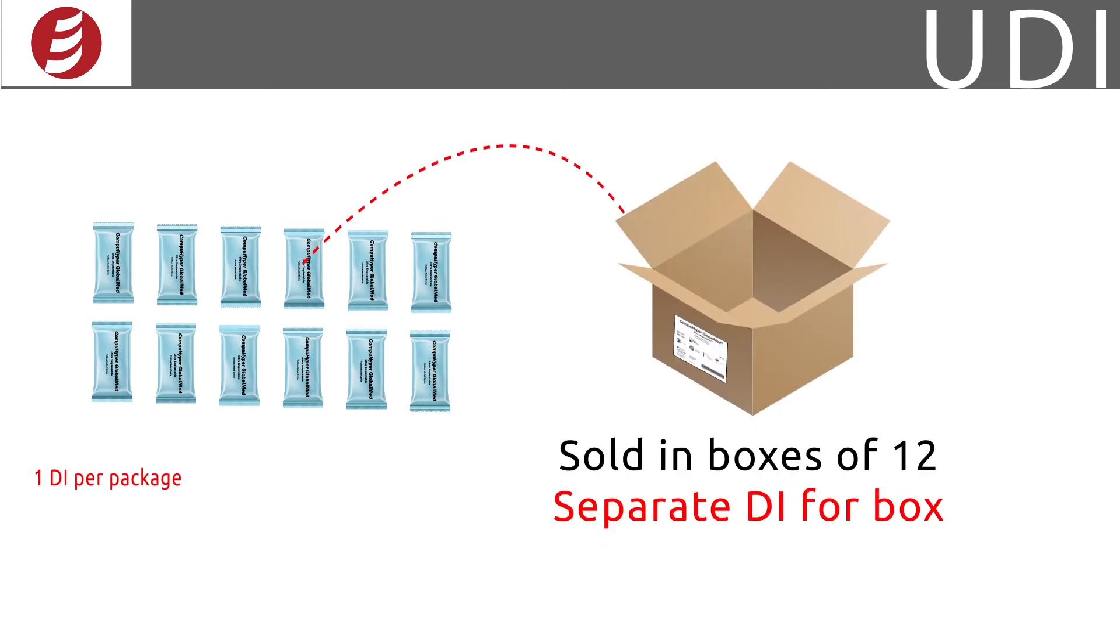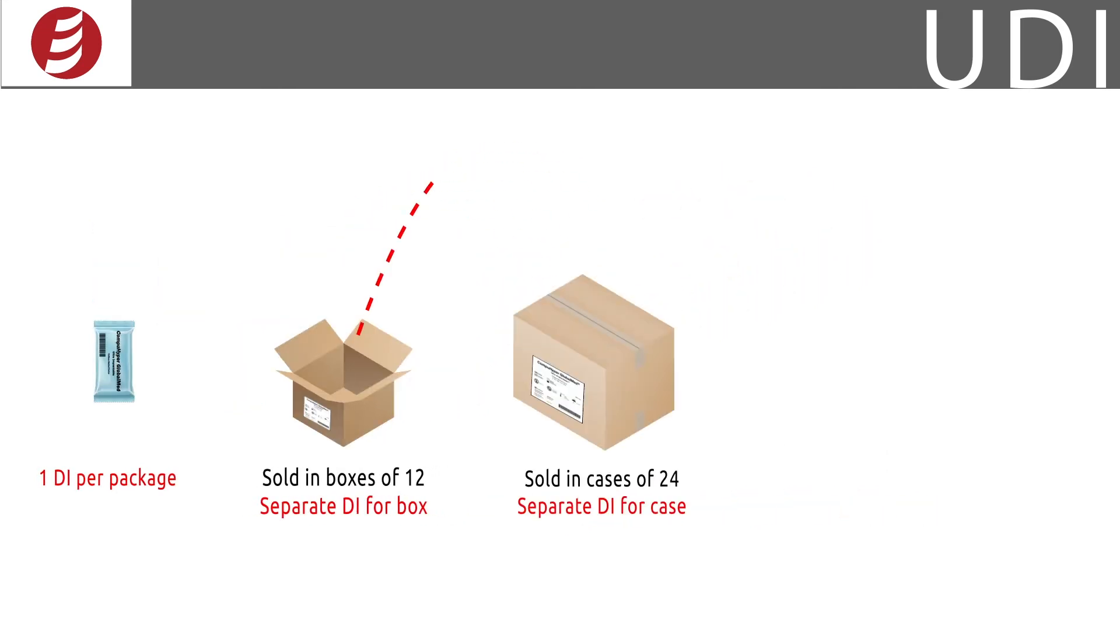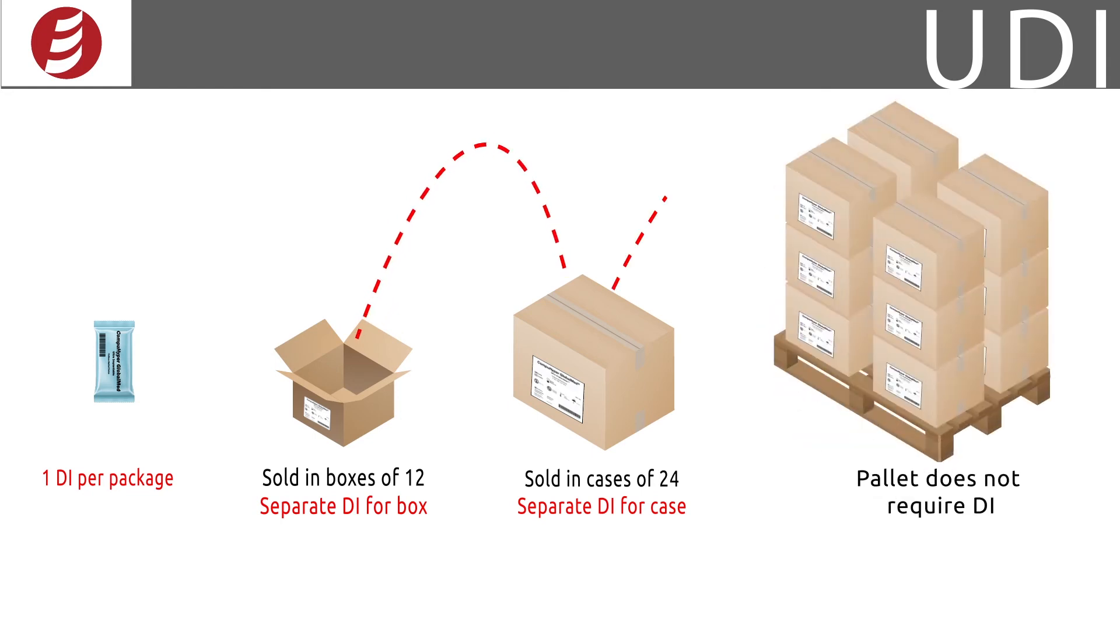If that box of 12 is sold in bulk as a crate or case, that higher level of packaging also is assigned its own DI. However, fulfillment packaging such as the shipping container, pallet, etc. does not require a DI number.